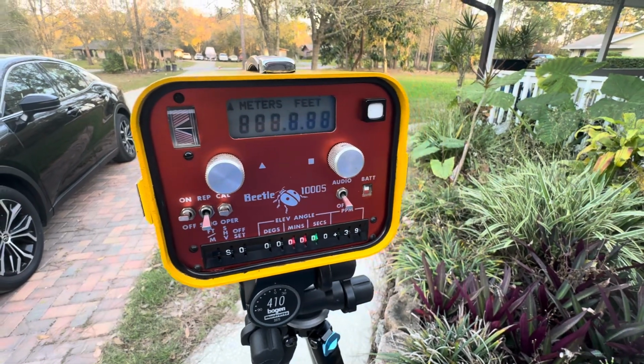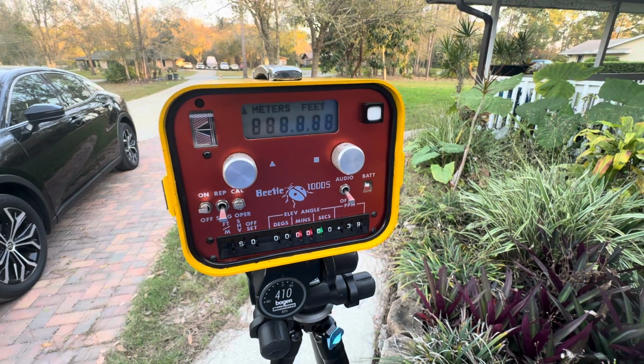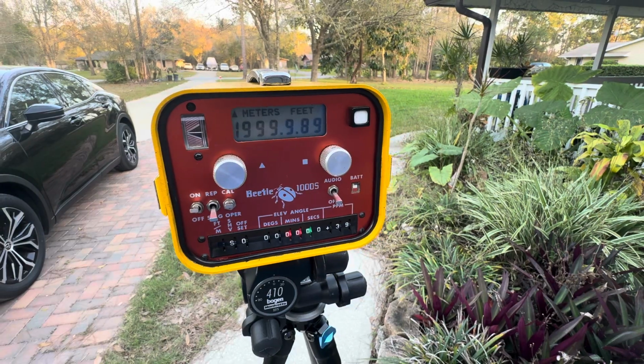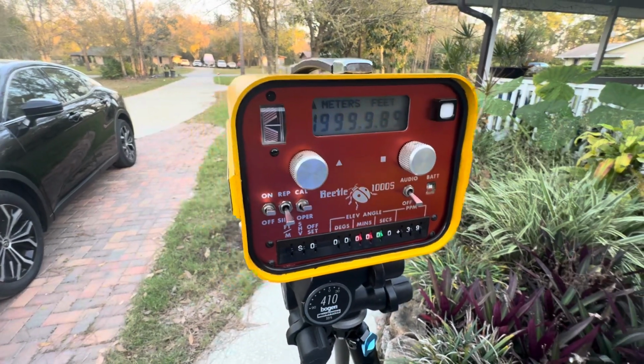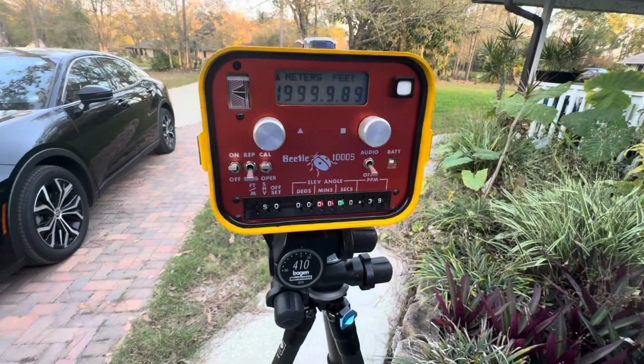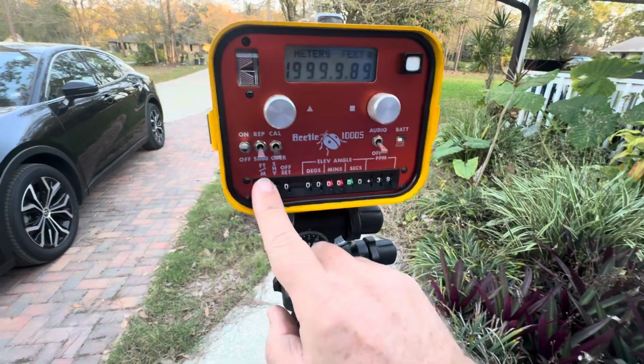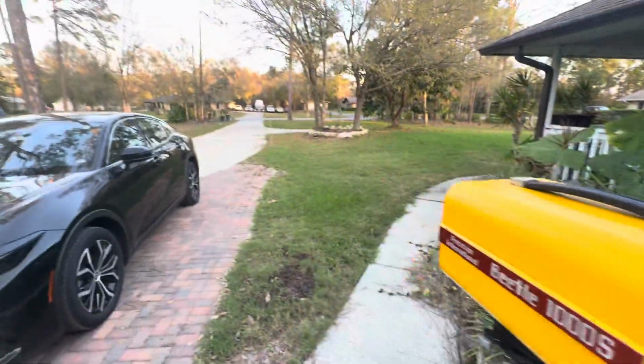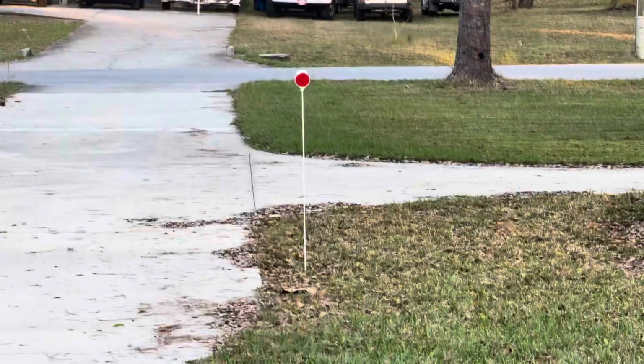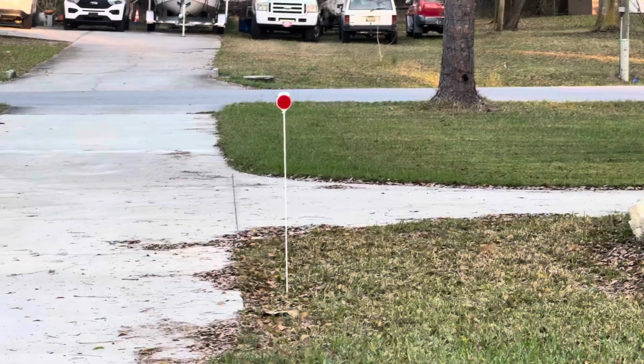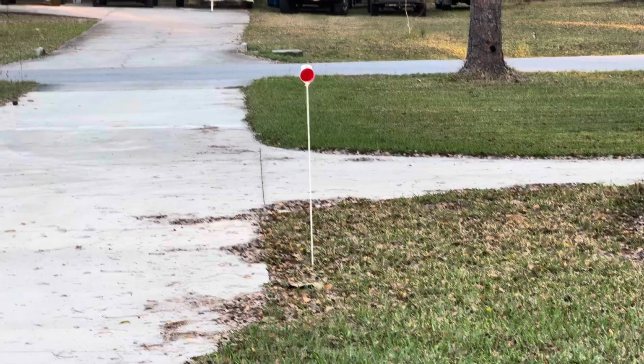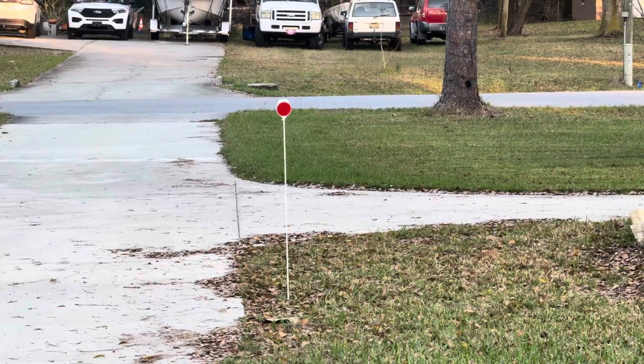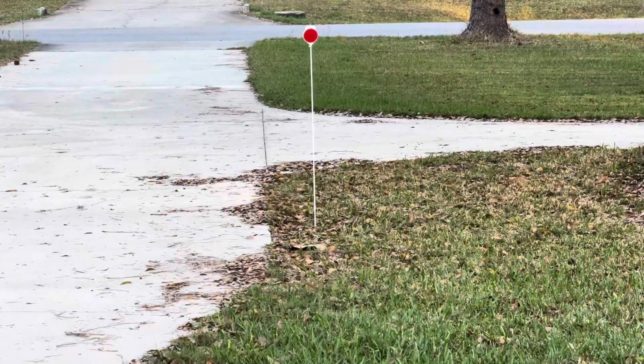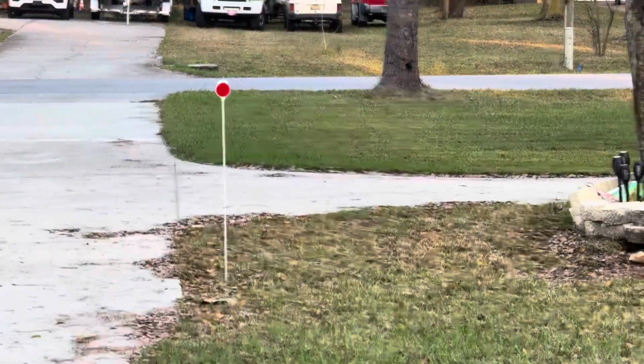Anyway, once you've got this stabilized, and it's been warmed up for about 5 minutes now, we'll do one more, see what happens. Yeah, there it is, 0.89. And so we're going to say that's going to be our calibration. You'd flick it off calibration to operation. I do it in feet because I have set out there a driveway reflector, which works out to about 100 feet or so. I haven't tested further than 100 feet. I also have an actual survey retro reflector. This is good for, I think, 1.5 kilometers or something like that, or maybe 1 kilometer. That's what the 1000 stands for.